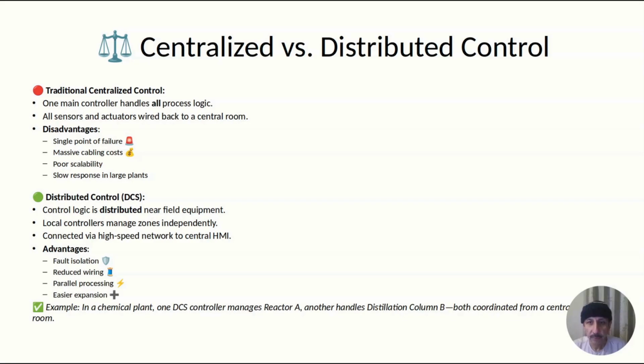DCS has flipped this model. By placing controllers near the equipment, we reduce the wiring, improve the response time, and isolate failures. If controller A fails, controller B keeps running. This shift wasn't just technical, it enabled the growth of mega plants like refineries and nuclear reactors and stations, where reliability isn't optional, it's existential.